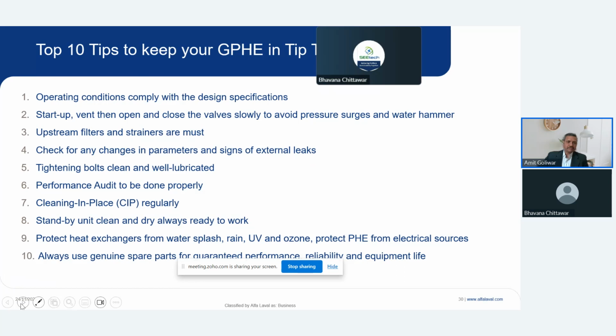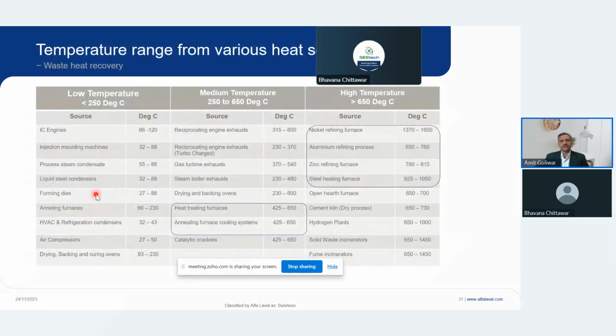With that, I would like to present this: many a time there is waste heat coming out of a process at a high temperature. Steel plants and many process plants, glass plants, wherever there is an oven or furnace, will generate it. Even the exhaust gas comes at a very high temperature, and it can be utilized. There are heat exchangers made to handle such high temperature exhaust gas as well.